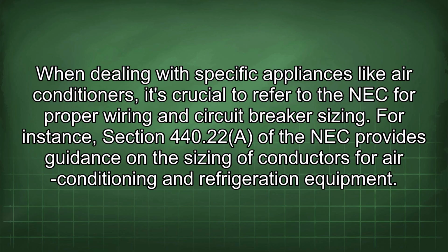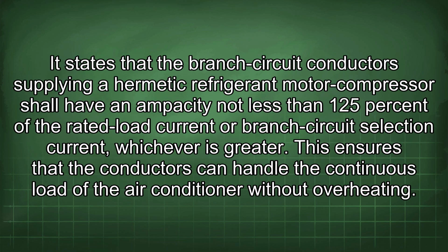When dealing with specific appliances like air conditioners, it's crucial to refer to the NEC for proper wiring and circuit breaker sizing. For instance, Section 440.22 of the NEC provides guidance on the sizing of conductors for air conditioning and refrigeration equipment. It states that the branch circuit conductor supplying a hermetic refrigerant motor compressor shall have an ampacity not less than 125% of the rated load current or branch circuit selection current, whichever is greater.